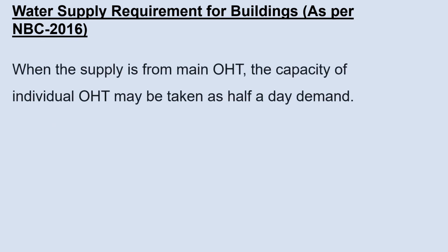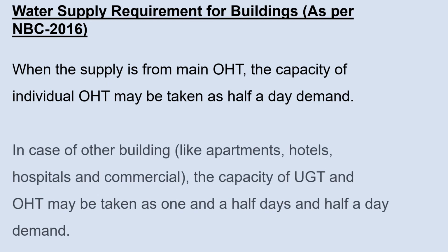When the supply is from the main overhead tank, the capacity of an individual overhead tank may be taken as half a day demand. In case of other buildings like apartments, hotels, hospitals and commercials, the capacity of underground tank and overhead tank may be taken as 1.5 day and half a day demand respectively.